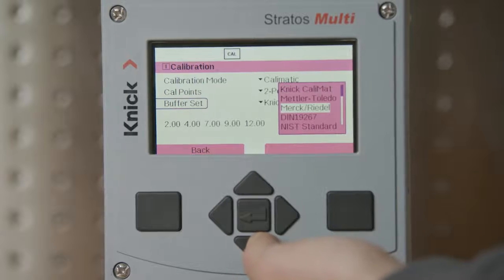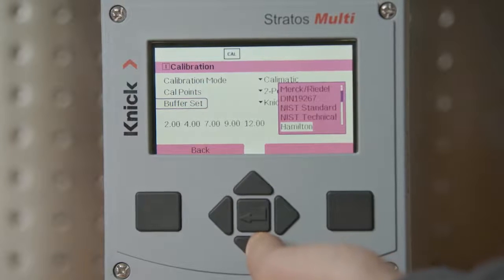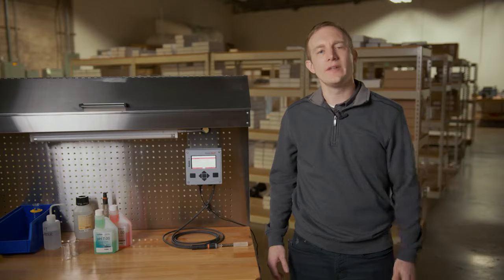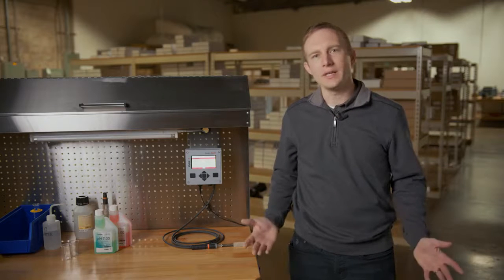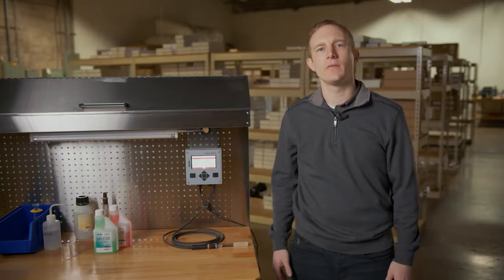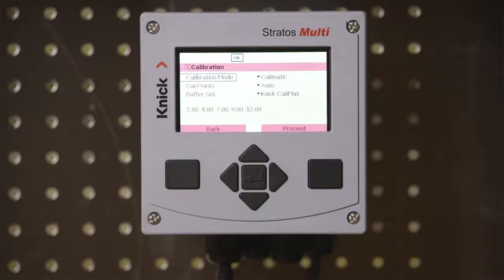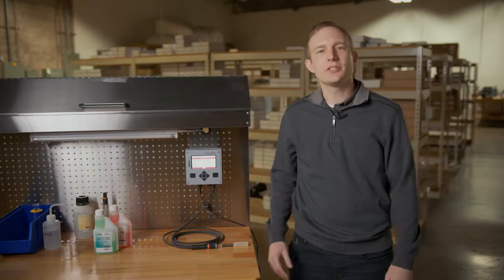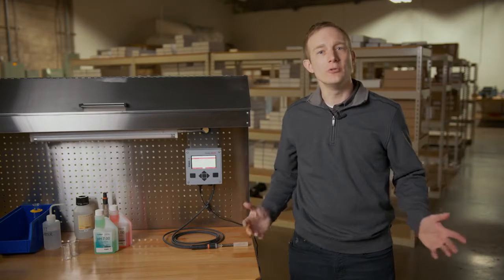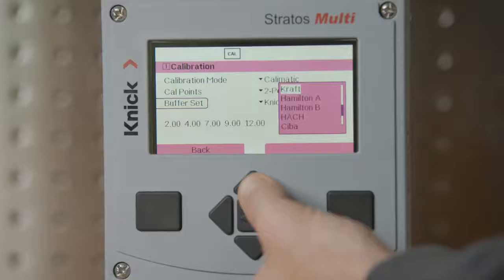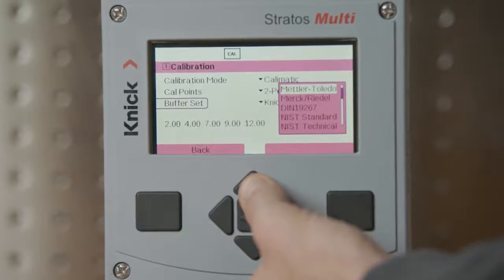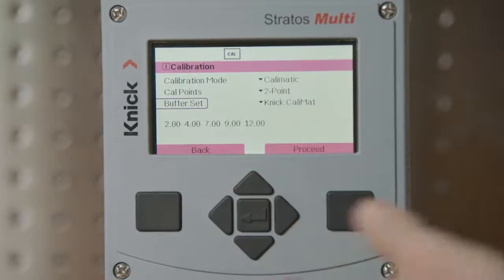The Multi has numerous buffer tables stored within its software for selection by the operator. It is important to note that NIST Technical is most commonly used. However, verification of your buffer values should be cross-checked against the values displayed at the bottom of the screen. A nice feature, which is also available for selection, is the ability to select a user-defined buffer table. We will select the Knick CaliMat buffers and press Enter to continue.